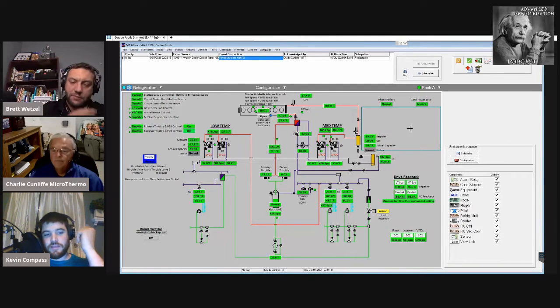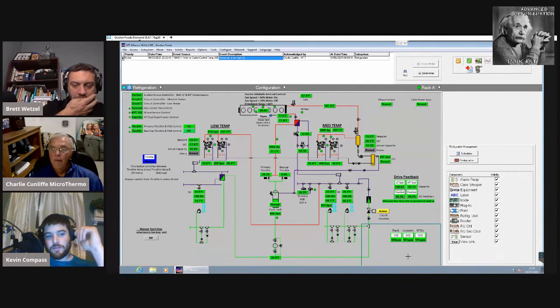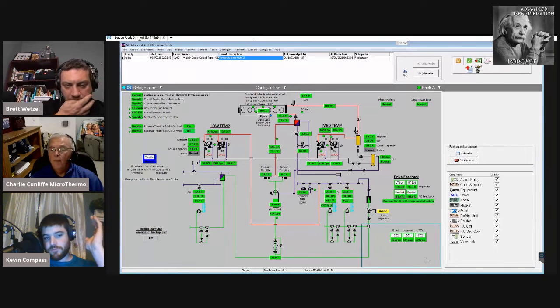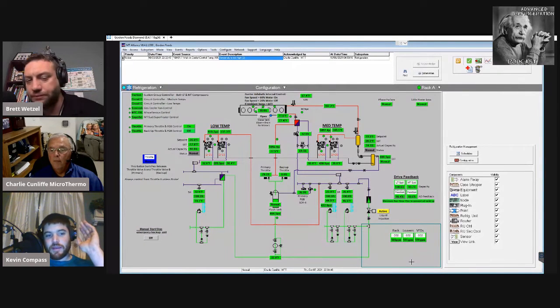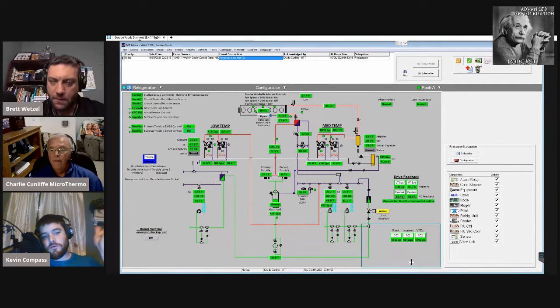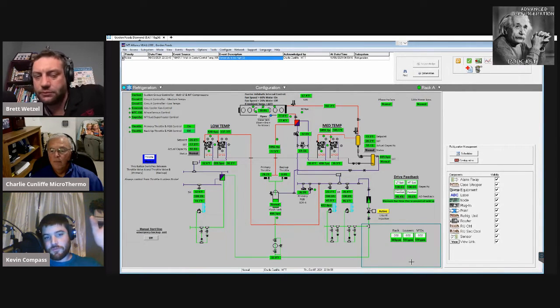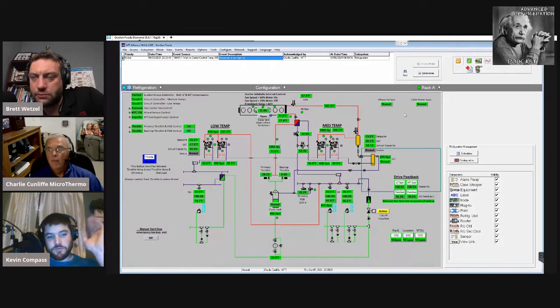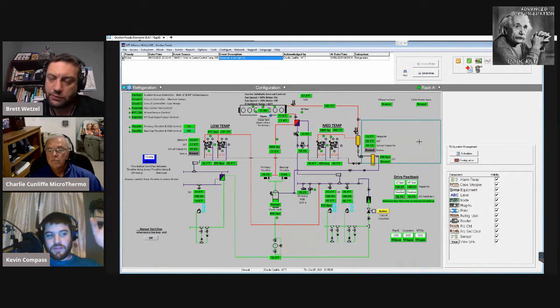It's the same way until you tune it. After you tune it, the MicroThermo one's just as good as the Danfoss one. It doesn't matter what it is, the stock settings never work. Everything has to be tuned, and that's the beauty about MicroThermo. You have more tuning set points in the MicroThermo two-valve controller than you do in the Danfoss, so you have a little more flexibility with it, and it's a little nicer in that sense.